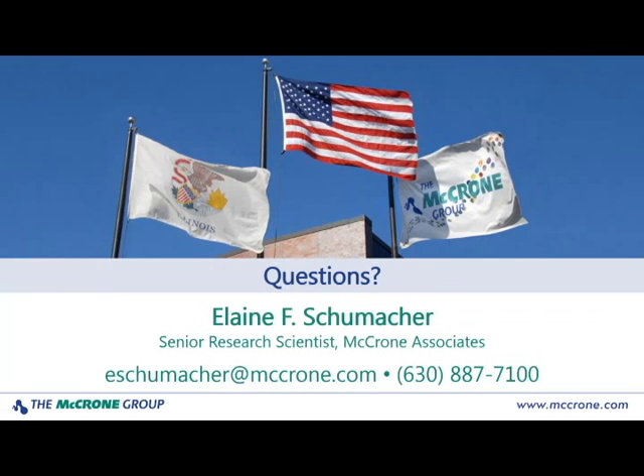If you just had very few delamination flakes of very small size on a filter, I think we'd need to check with one of our clean room microscopists to see what's the lower limit of what they can see with that particular type of material. That's a good question. And the coaxial illumination is key for that analysis as well. But we'll follow up with that.